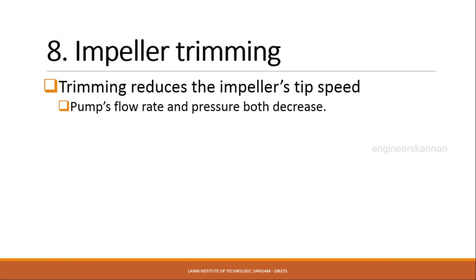The next parameter is impeller trimming. Trimming reduces the impeller tip speed, which in turn reduces the amount of energy imparted to the pumping fluid. As a result, the pump's flow rate and pressure both decrease.